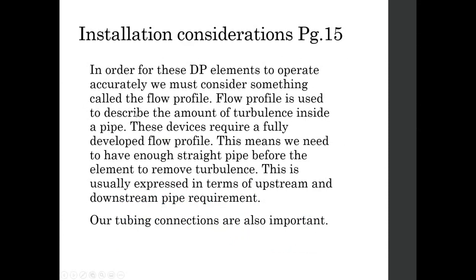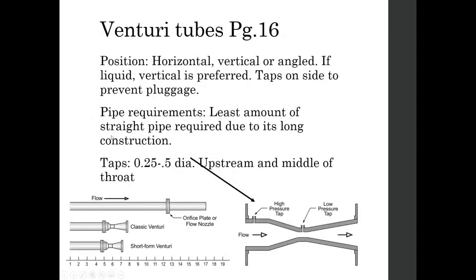Moving on to the next objective — installation considerations for these different flow elements. In order for these elements to operate accurately, we must consider the flow profile, which describes the amount of turbulence inside the pipe. These devices require a fully developed flow profile, meaning we need enough straight pipe before the element to remove turbulence. This is usually expressed in terms of upstream and downstream pipe requirements. Tubing connections are also important — things like reaming out your tubing — a minor detail but can be important in the big picture.